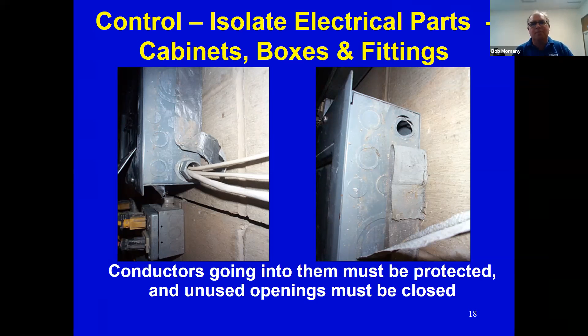There was actually a fatality that happened down in the Dayton area where exactly that same thing happened. He took a cover off of a box. There was dust that accumulated on top. The dust fell into the box when he took the cover off, and unfortunately he was fatally injured. So it does happen. That's probably the more common thing that I've seen out there, where these boxes don't have the covers on them. The knockouts that you have on here are left open as well. So we need a cover on this box. We need to have plugs put in here so we don't have open knockouts in there. And that controls our shock and fire hazard.